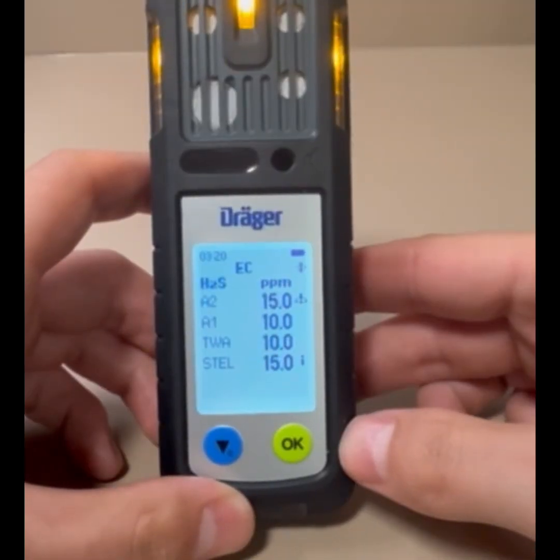And finally, your H2S sensor, or hydrogen sulfide sensor. This is also a two-alarm system, with alarm 1 being at 10 parts per million and alarm 2 set at 15 parts per million. You can also display your time-weighted average, or TWA, of 10 parts per million, or your STEL, short-term exposure limit, set at 15 parts per million.